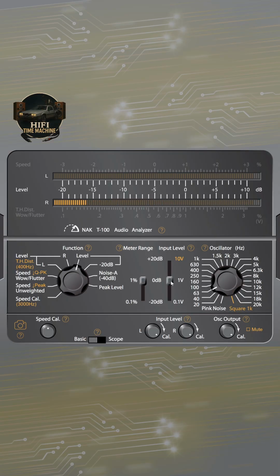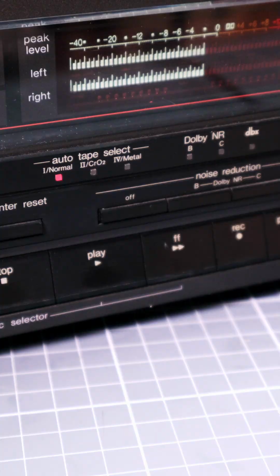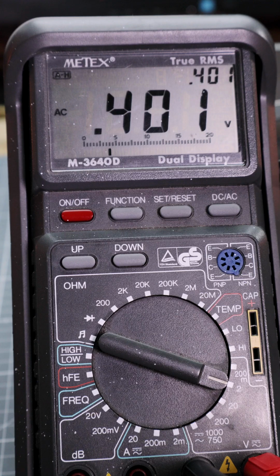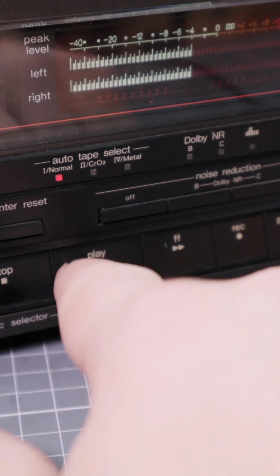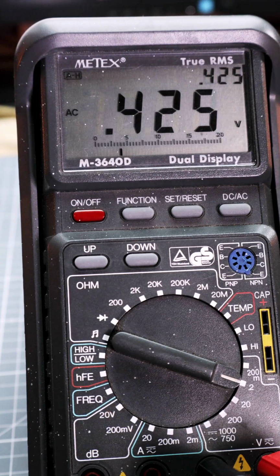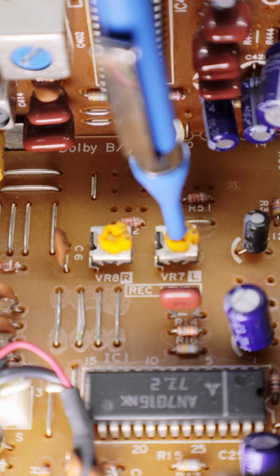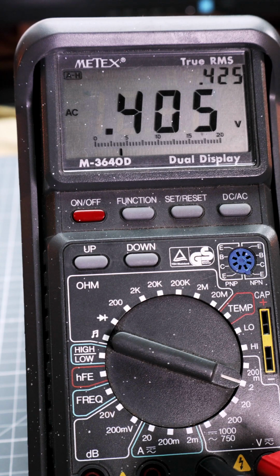I applied a 1 kHz signal with a defined level for the final setting, the overall gain adjustment. This is intended to match the recording level. The applied signal is recorded, and the recording level is then adjusted to the input level using 2 additional potentiometers. Both levels must be the same.